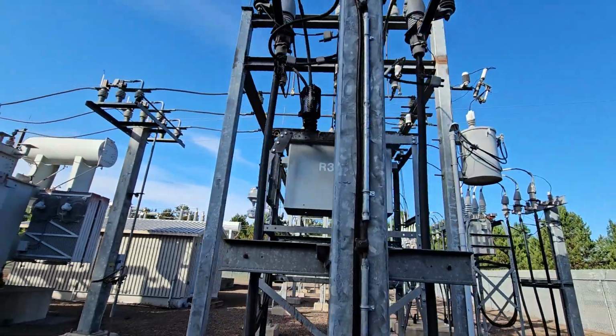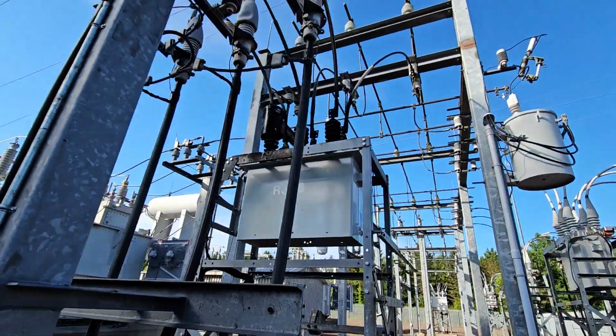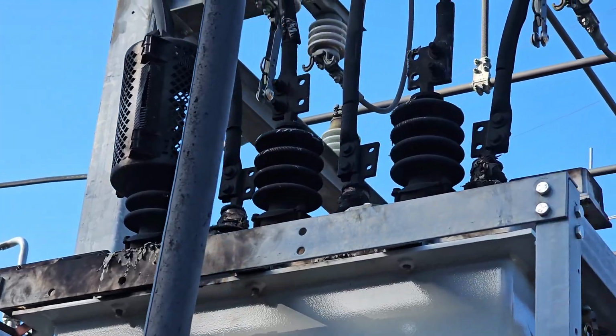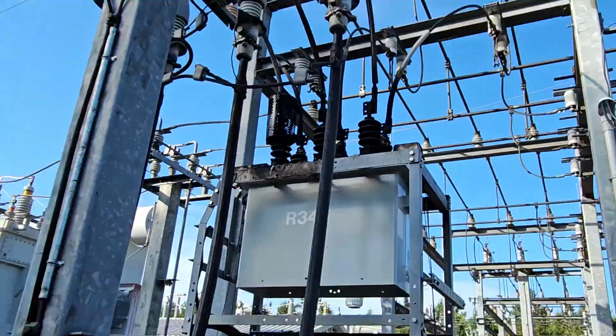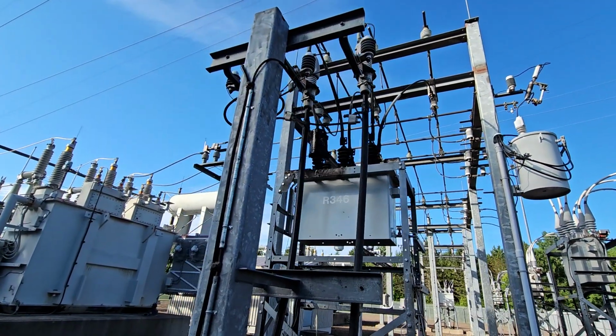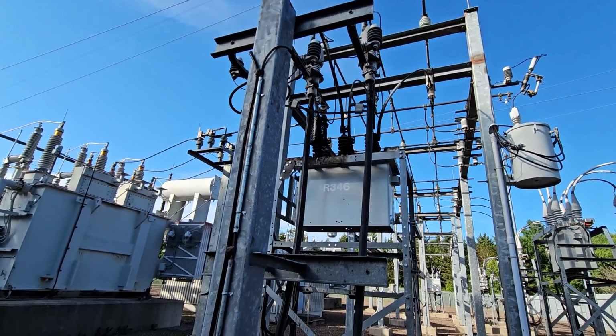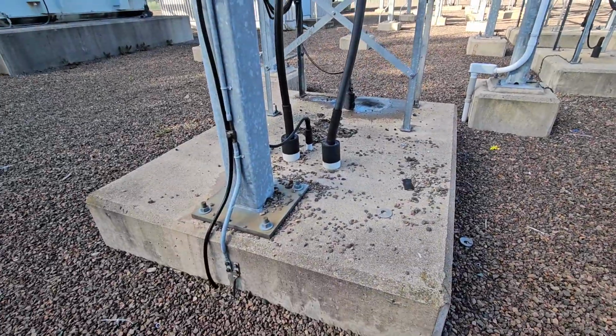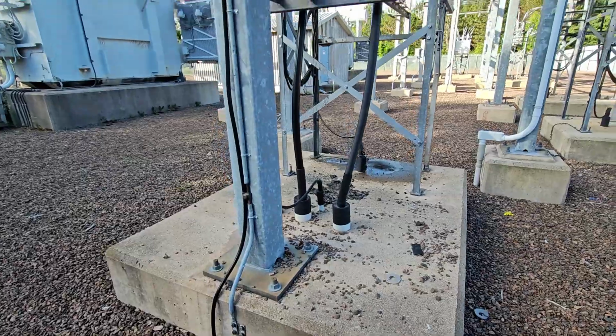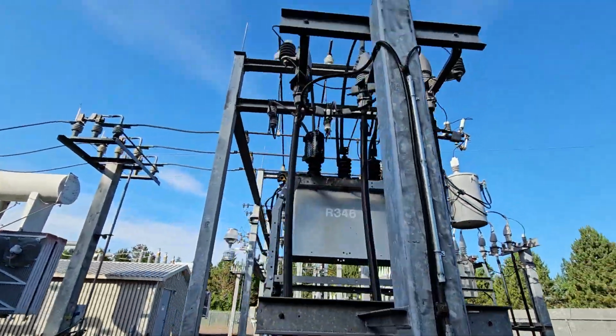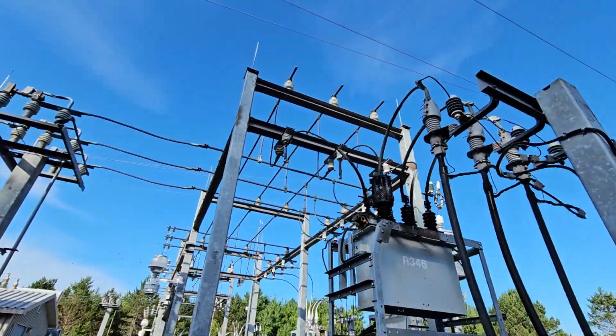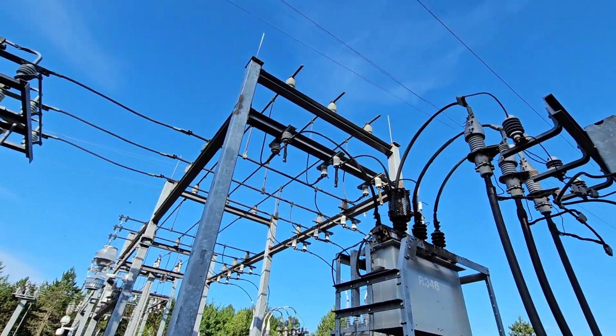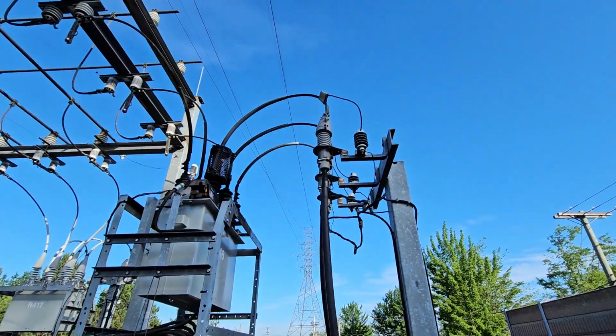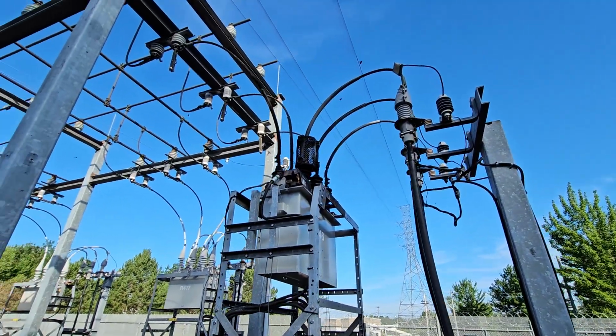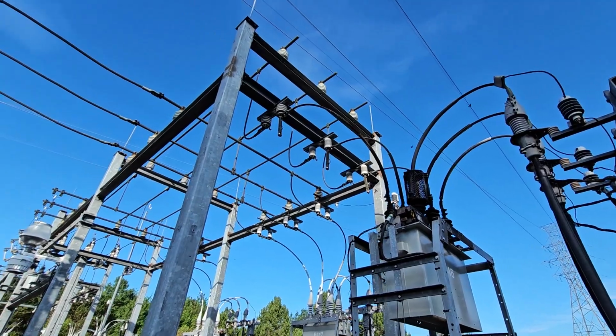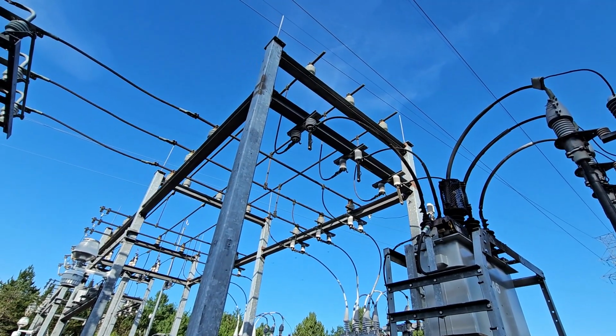This recloser here, she gone. It was actually on fire when we arrived. That part, not a difficult fix, a little bit time consuming. We have to replace the entire unit. You can see on the ground where everything was melting from what was on fire. But basically, all I had to do was isolate the recloser from those switches. If there was a fault on this side here on the cable side, the recloser would have opened, but the whole thing was on fire. So that's why we've got it isolated with those underslung switches there.